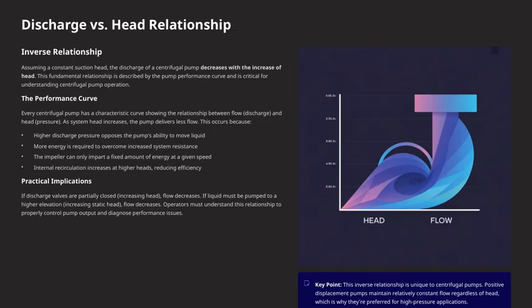Let's take a closer look at the relationship between discharge and head in centrifugal pumps. This relationship is inverse, meaning that as the head increases, the discharge decreases, assuming the suction head remains constant. This fundamental concept is captured by the pump performance curve and is essential for understanding how these pumps operate in real-world conditions. Now, every centrifugal pump has what we call a performance curve. This curve shows us how the flow rate, or discharge, relates to the head, or pressure. What you'll notice is that when the system head goes up, the pump delivers less flow.